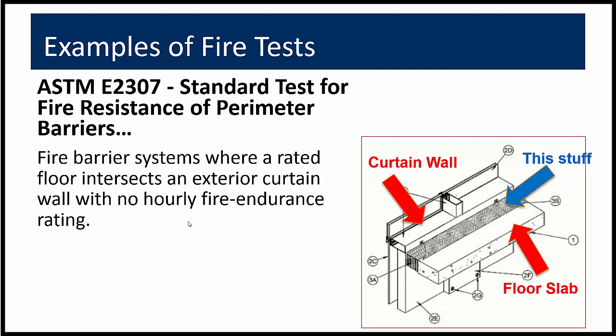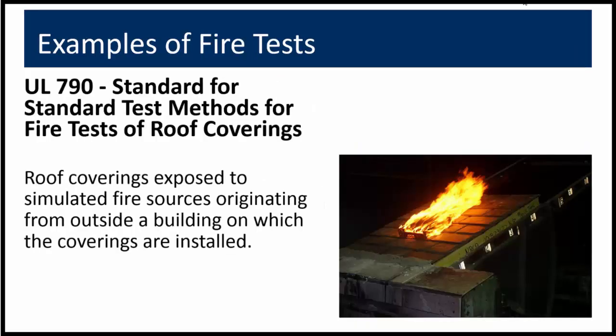This is a familiar topic to many project managers within WJE. UL790 measures the relative ability of a mock-up roof covering to withstand simulated fire sources. This applies to the roof covering, and it is intended to apply to fires originating from outside of the building on which the covering is installed. This test applies to roof coverings for both combustible and non-combustible roof decks, and you may know the resultant ratings as Class A, Class B, and Class C roof coverings.